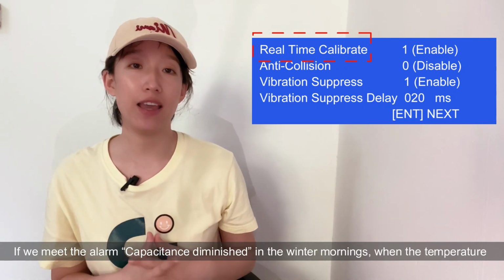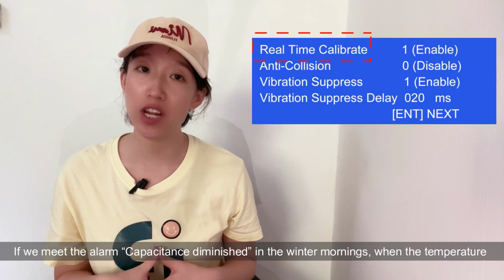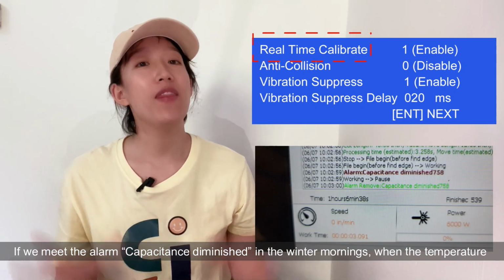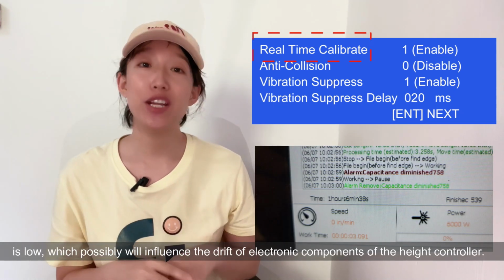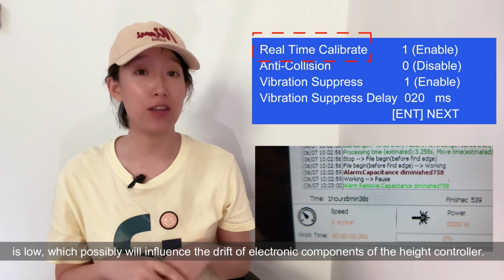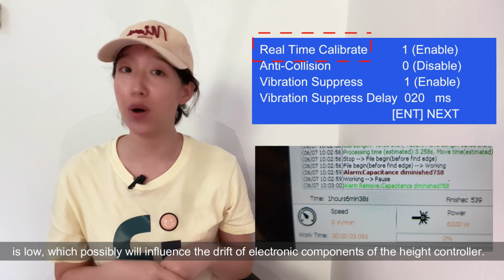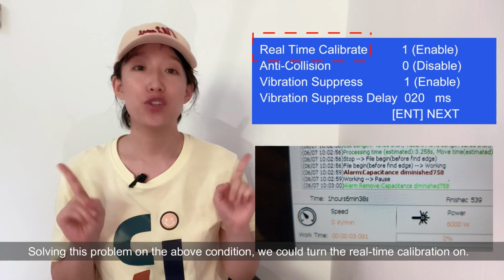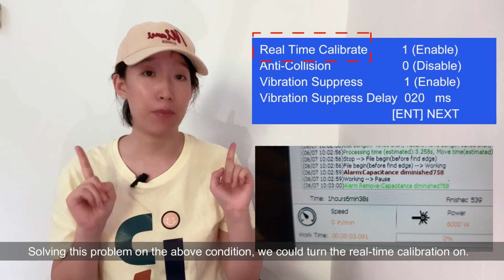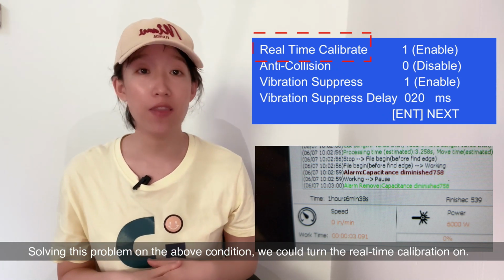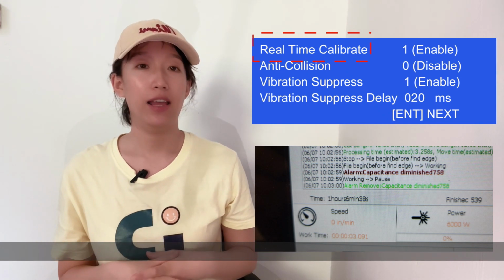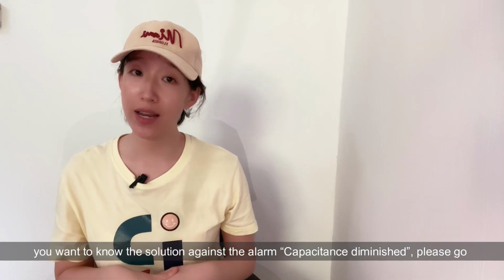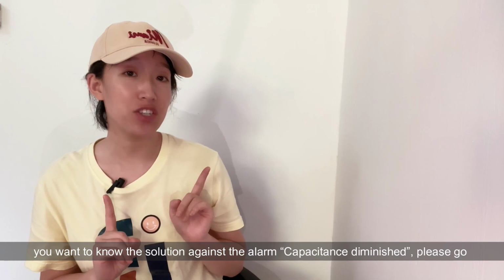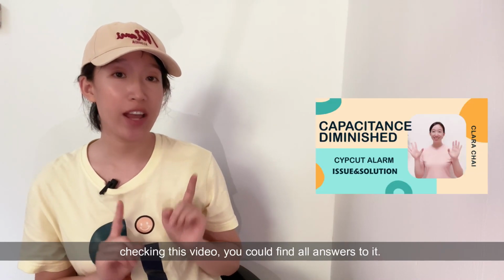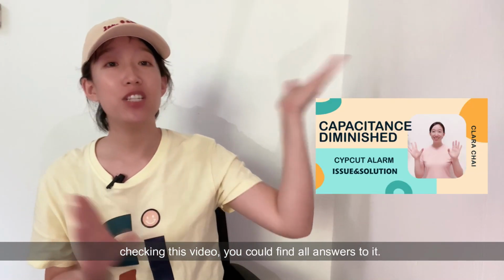If we meet the alarm capacitance diminished in the winter mornings when the temperature is low, which possibly will influence the drift of electronic components of the height controller, to solve this problem on the above condition, we could turn the real-time calibration on. If you want to know the solution against the alarm capacitance diminished, please go check in this video. You could find all answers to it.